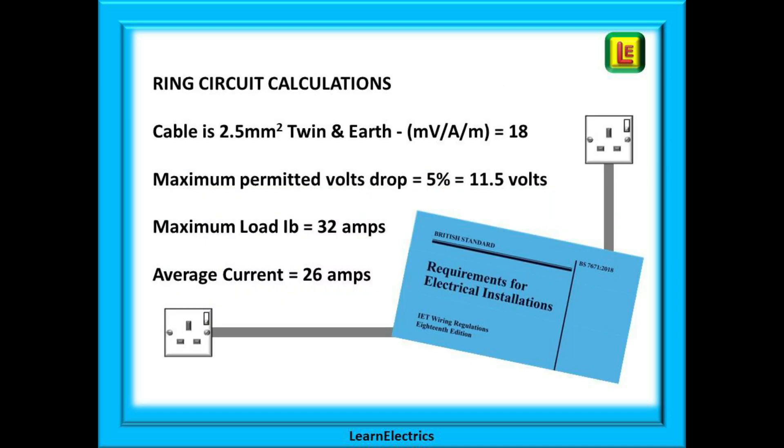For our calculations we've agreed the cable will be standard 70 degree gray 2.5 millimeter twin and earth. From the tables in the regulations we found that the MVAM number for this cable is the number 18. This tells us that our 2.5 cable will lose 18 millivolts for every amp that flows through every meter of cable.